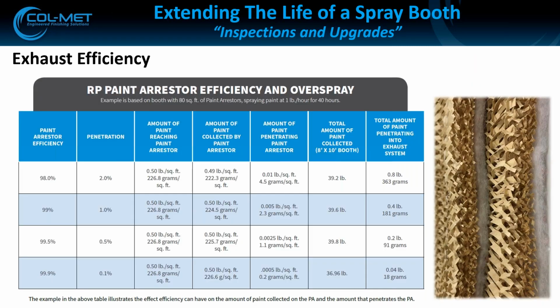But the main thing that you have to understand when it comes to filtration is that you're required by code to have a 98% arrestance on that filter, right? And that's done with a test that requires it to be sprayed at a certain volume with a certain type of paint to meet that 98. And that certain type of paint is a Sherwin-Williams Permaclad bake-on enamel. Okay, so it's pretty sticky, high viscosity. It's honestly kind of hard for a filter not to get close to or be 98%.